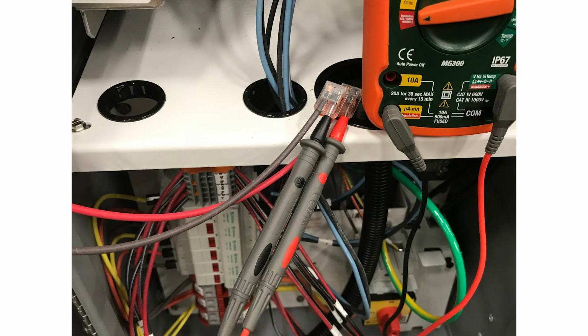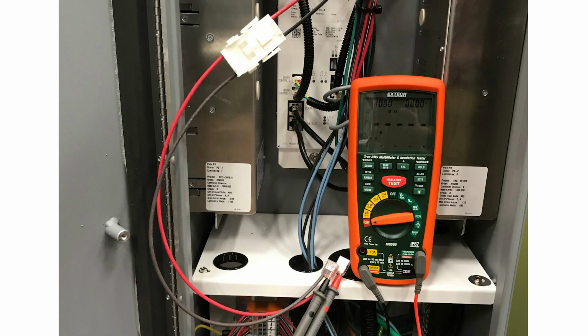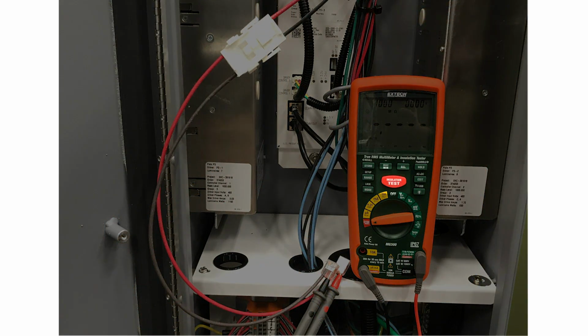Hook your meter up red to red and black to black, then press the insulation test button and hold for 45 seconds, recording both resistance and voltage, if your meter gives you a voltage reading. Testing will cause the fixture to glow, but it may not be visible from the testing location. Once you have a baseline set, you may proceed to testing the outage.